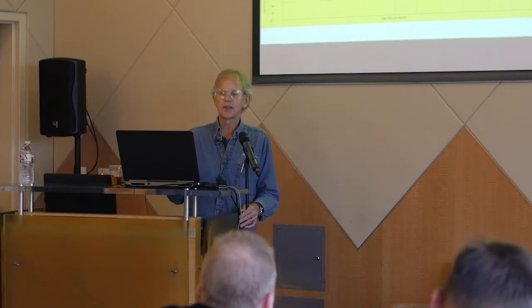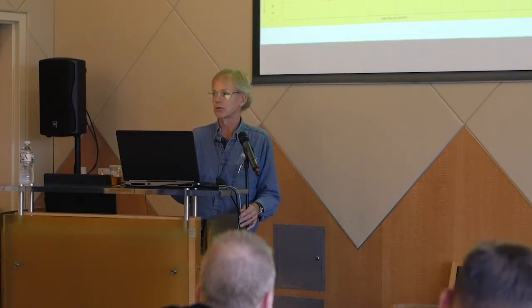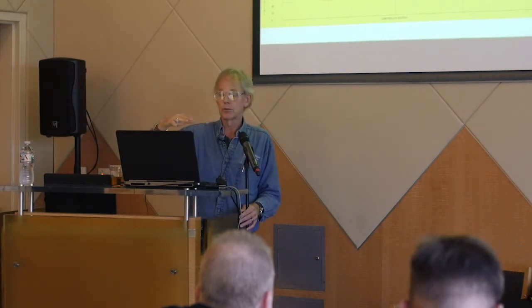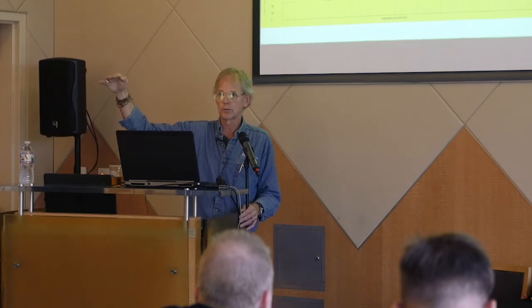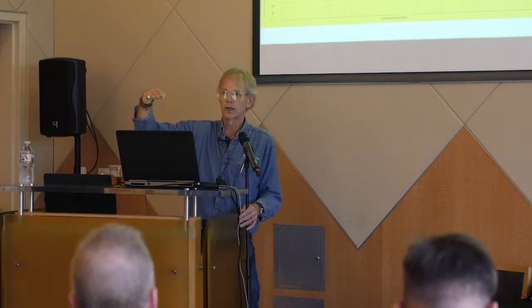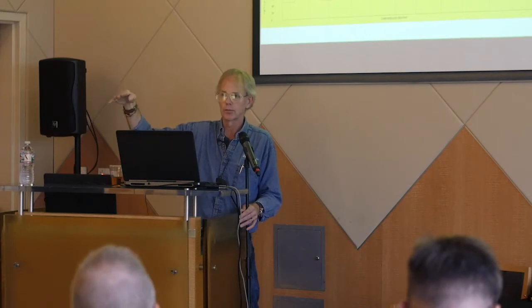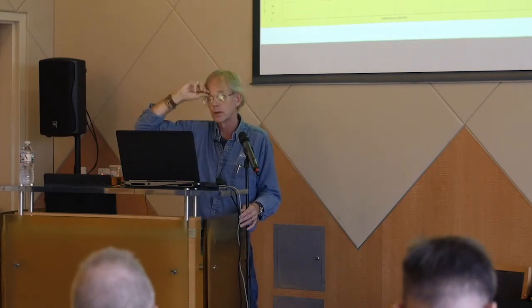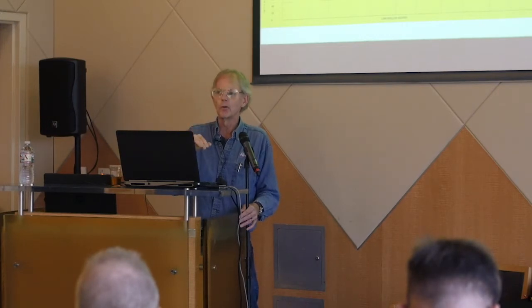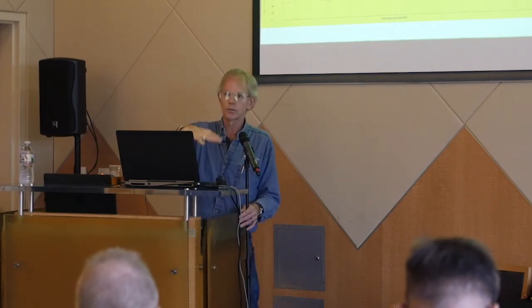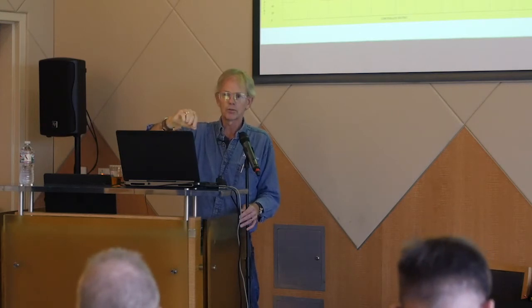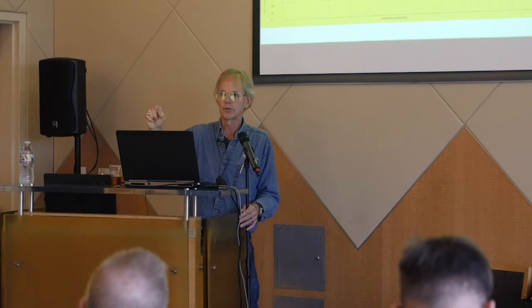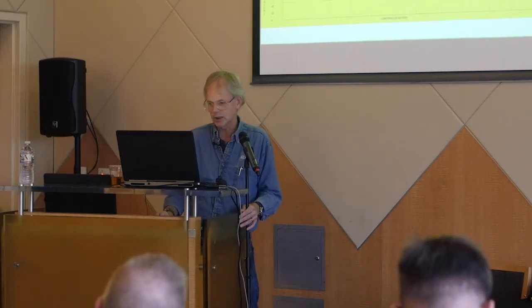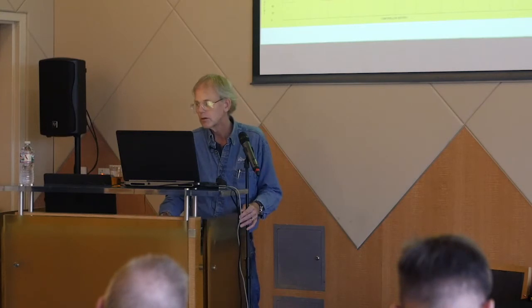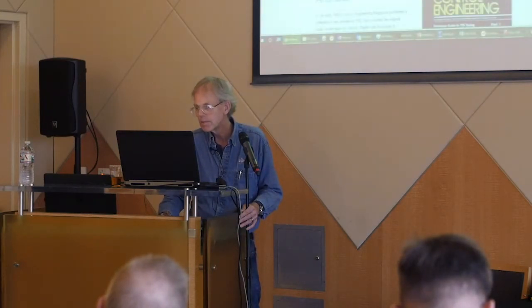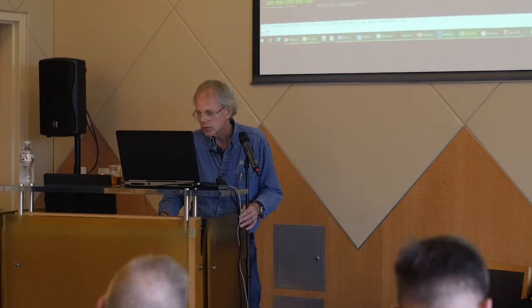Back in the olden days, one of the advantages to being my age is you got to mess with pneumatics. That's how you learned this stuff. And so back in the olden days, it was not uncommon at all to have all these pressure electric switches on an analog signal. And the pressure electric switches stage the compressors, the duct heat, tower fans, whatever you're trying to control. And so in a way it was a benefit, because not only could you mess with the proportional gain of the controller, you could mess with the set points and the differentials on the pressure switches. So I think like the electronic analogy of that, let's see.